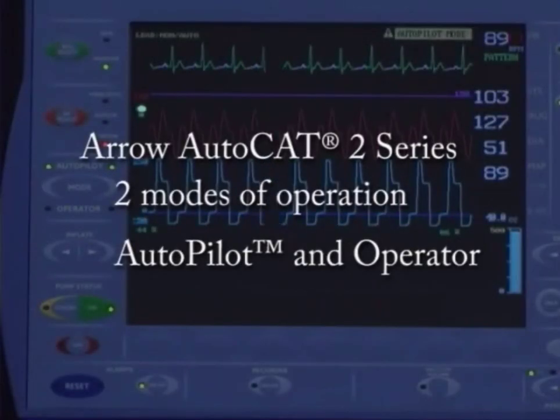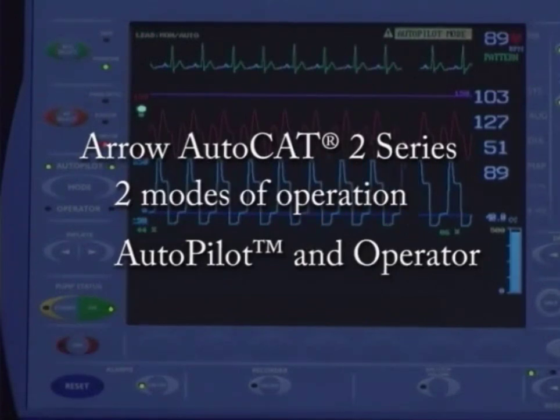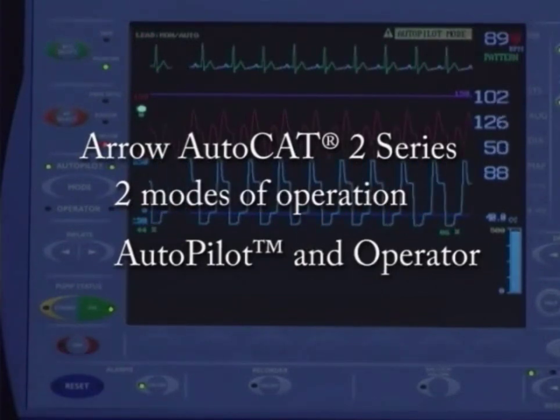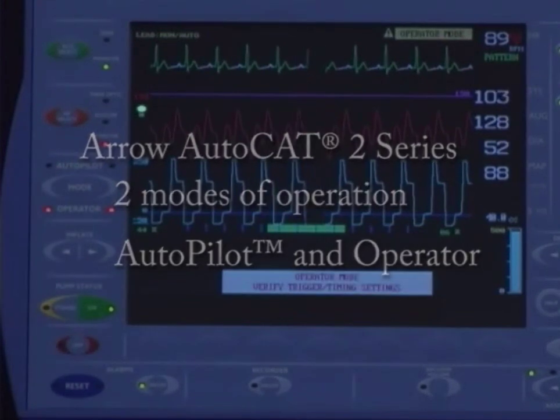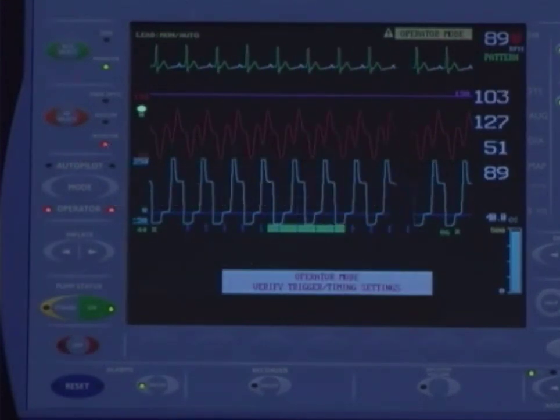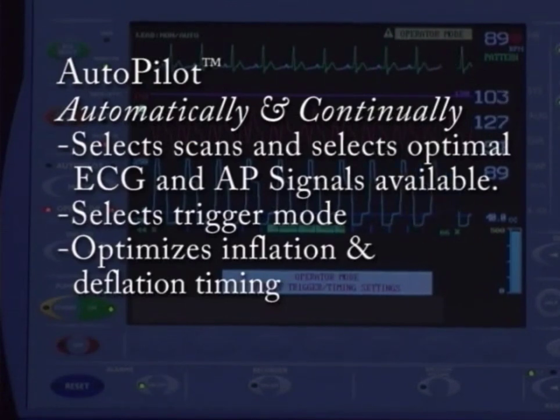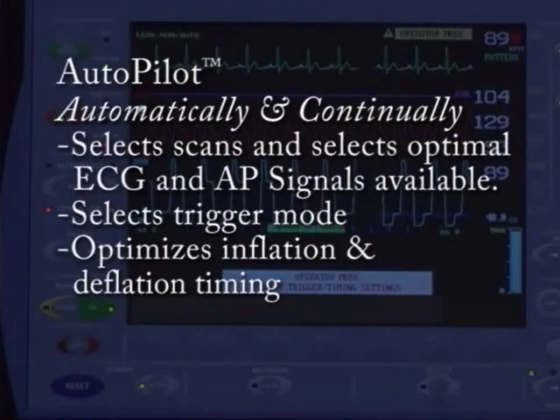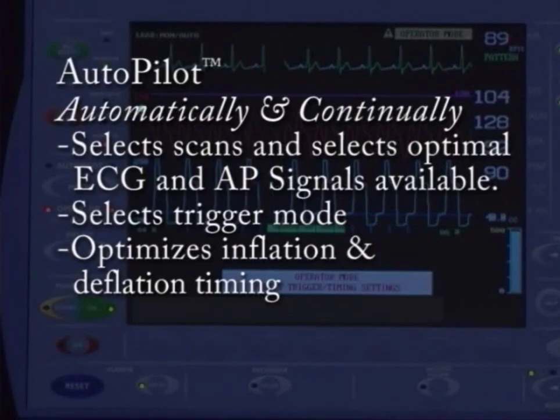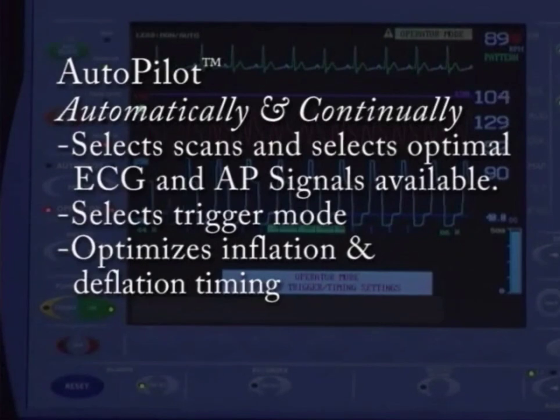The Arrow AutoCAT 2 series offers two distinct modes of operation: AutoPilot and Operator. AutoPilot mode puts the pump in charge of all of these functions for you, allowing you more time to spend with your patient. Arrow's AutoPilot features automatic ECG and AP signal recognition and selection. Automatic ECG lead selection uses best signal analysis. It will choose the appropriate trigger and timing method based on a patient's condition and signals connected, and will maintain optimal timing.